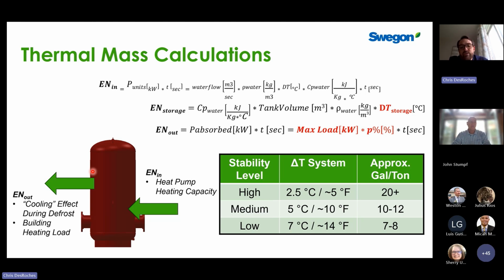So at Swegon, we group this into what we call temperature stability levels. We would call it low stability, medium stability, or high stability. In other words, for low stability, we size the volume such that in the worst case of defrost, we only see a temperature drop on the system of X degrees. For low stability, X corresponds to about 15 Fahrenheit. For a medium stability system, we size the water volume such that we only see a worst case temperature drop of 10 degrees Fahrenheit. We almost never size for high stability. It just results in way too much water that's needed.